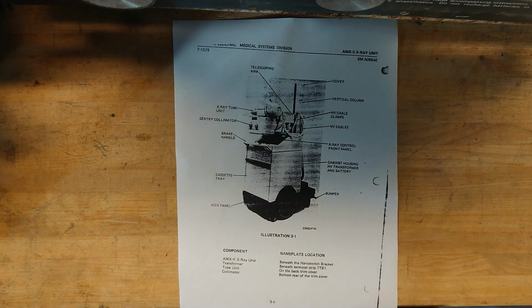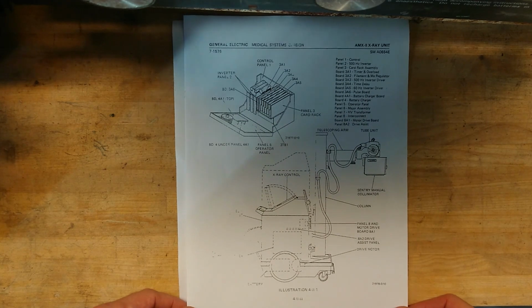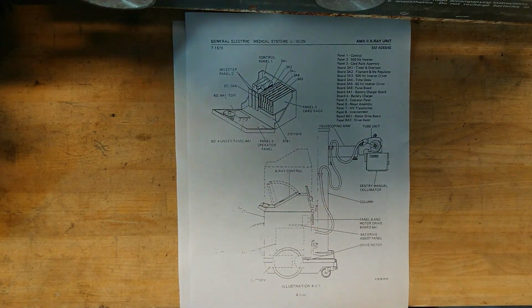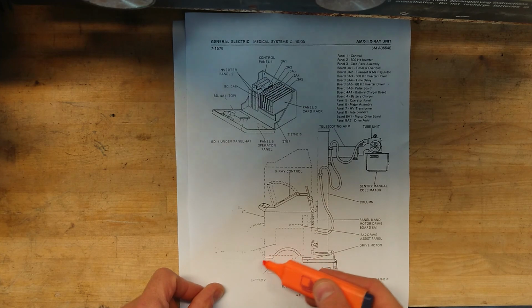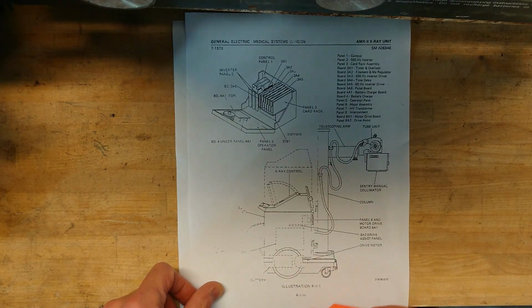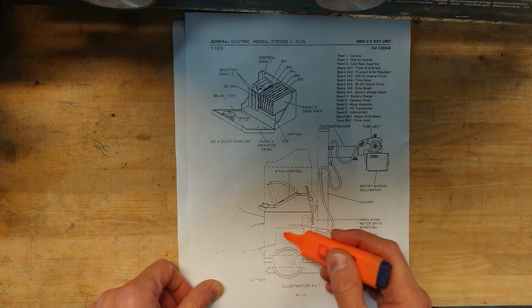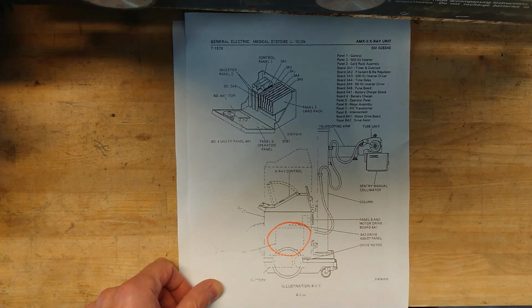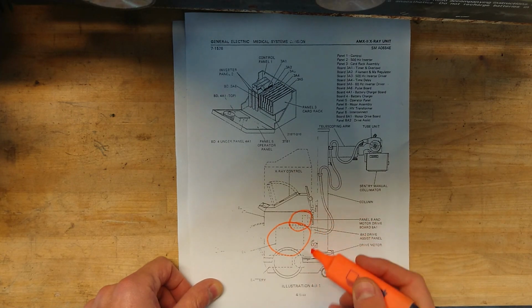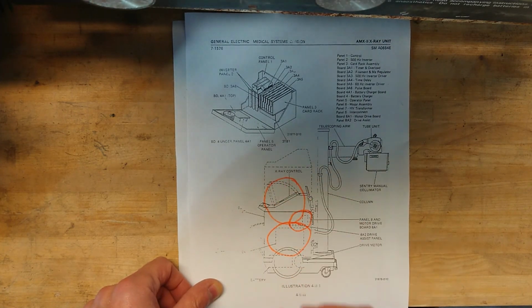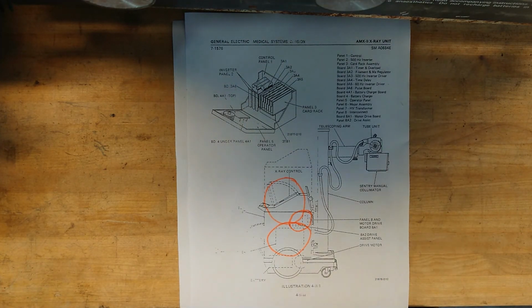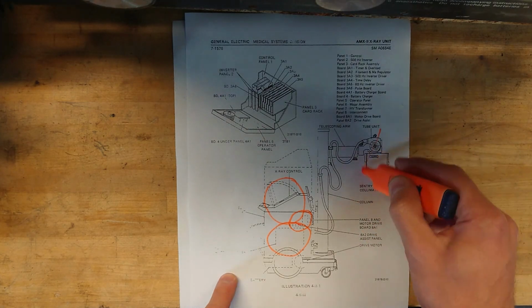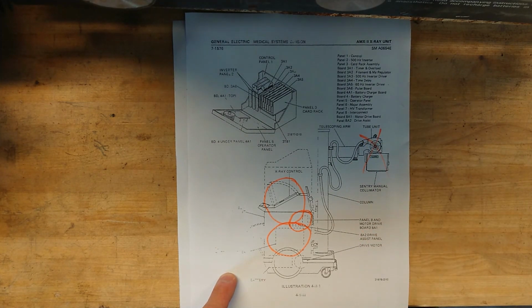Now if we take a look at a breakdown here of the unit, we can see that we have the battery pack down here at the bottom to keep the center of the weight very low for the unit. Now what I have is the high voltage transformer. I got the motor drive board, and I got the whole X-ray control unit, and that's about it. The rest of the unit was badly damaged, and the head was completely missing. So those things had been taken away before it was thrown out.